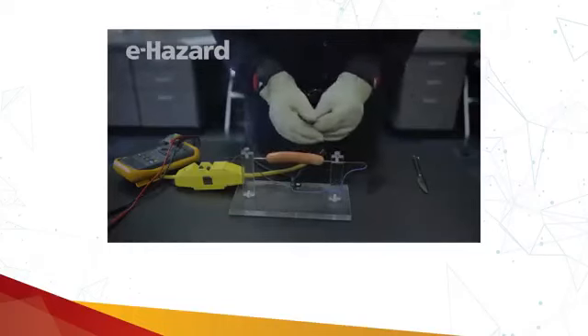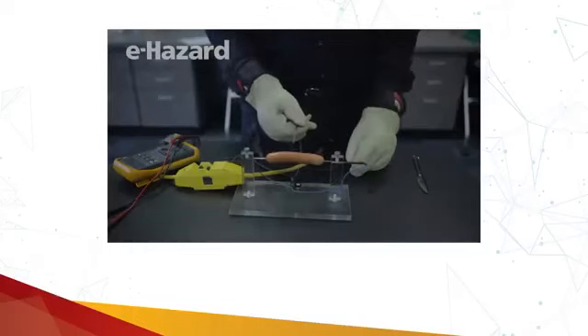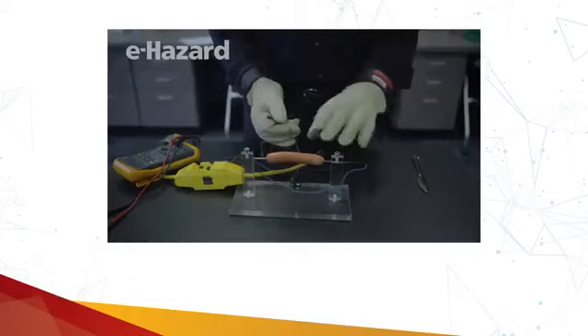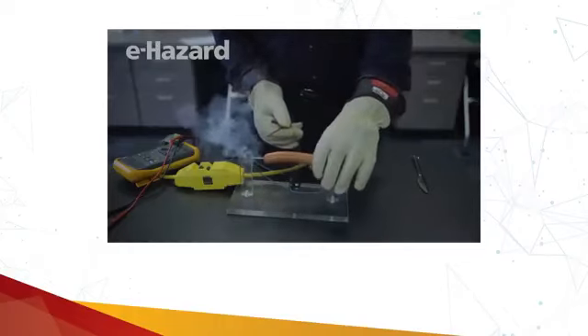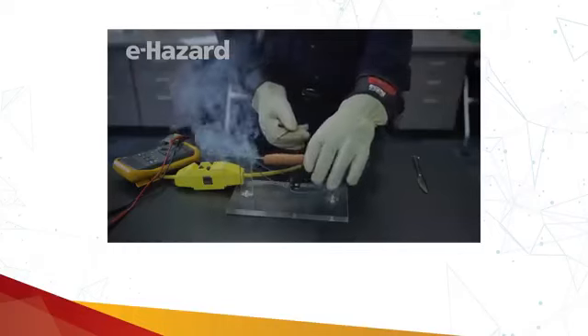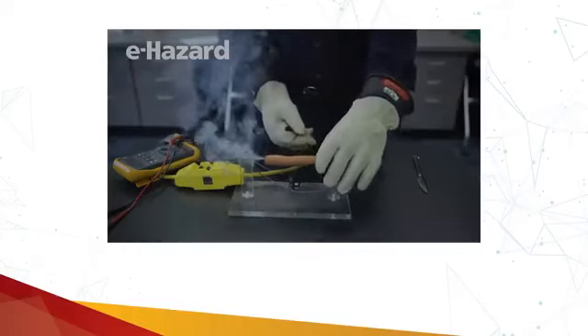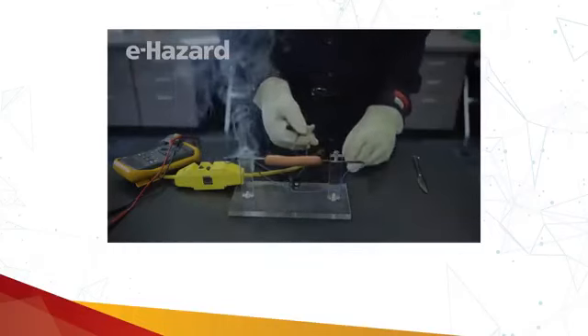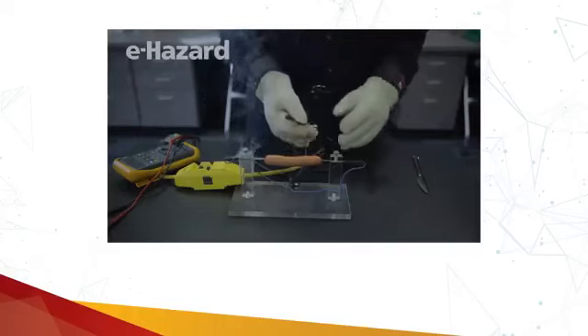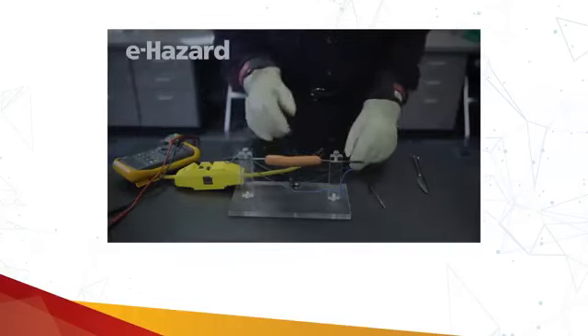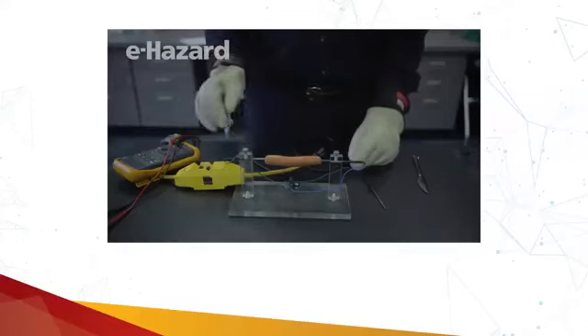So let's look and see what happens. As soon as I establish a ground, I should hear my GFCI trip, right? Charlie's sitting here just cooking away, but externally, do you see anything? No. Watch. Did you hear the GFCI trip? As soon as I got a ground circuit, my GFCI tripped.